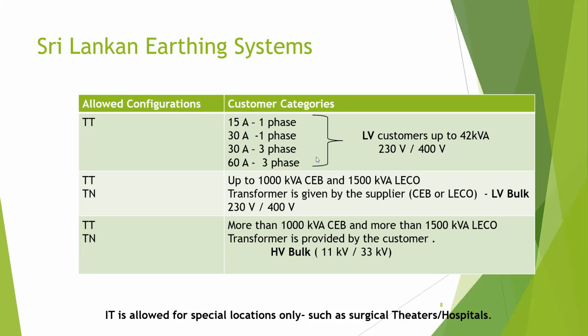So for LV bulk customers, if you request a supply from your electricity supplier, they will provide you with a free transformer. That means you have a dedicated transformer for your premises. So in that case you can have TT or TN. If you are getting your power supply from a common transformer, meaning one transformer is feeding a lot of houses, you can't have TN, you can only have TT. But if you have a dedicated transformer at your place, you can have either TT or TN. Usually in SLIIT, our new engineering faculty is wired in a TN system. There are several TN subcategories, and we are going to learn about them in a few slides.